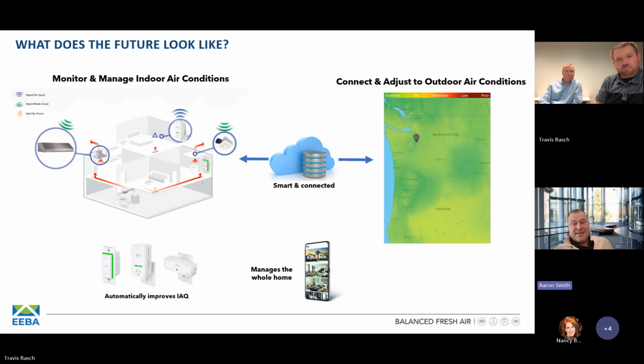And maybe my final comment is I got to see this at the EEBA summit, but the Overture outlet product in the bottom left of this, you could take that 50-year-old bath fan, that Broan-NuTone that's still running, and you can add that to the outlet, and it now makes it a humidity and motion sensor and kind of makes that old bath fan a heck of a lot smarter. Because you always worry about the occupants, the kids not turning it on, right? Yep, exactly. No, you're absolutely correct. I've seen a lot of retrofits because of how simplistic it is to basically add on that feature and maintain the exhaust ventilation device you got. So it's fantastic.